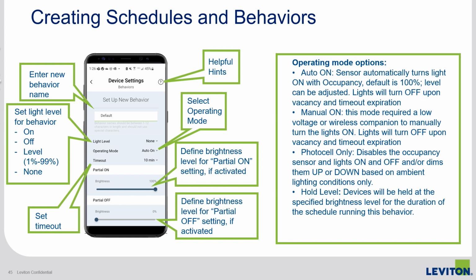Next is Photo Cell Only. In this mode, the occupancy sensor is disabled and the lighting will only change based on changes to ambient light levels. The last operating mode is Hold Level. With Hold Level, the lighting will be held at a specific brightness or level for the duration of the schedule running the behavior. Occupancy events and photocell readings are ignored in the Hold Level mode.